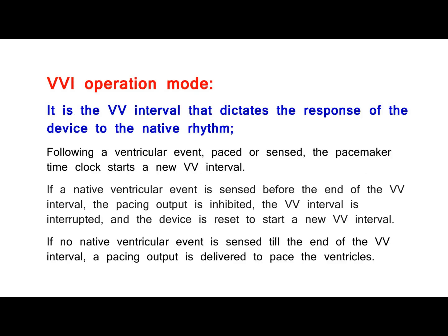VVI operation mode. It is the VV interval that dictates the response of the device to the native rhythm. Following a ventricular event, paced or sensed, the pacemaker time clock starts a new VV interval. If a native ventricular event is sensed before the end of the VV interval, the pacing output is inhibited, the VV interval is interrupted, and the device is reset to start a new VV interval.